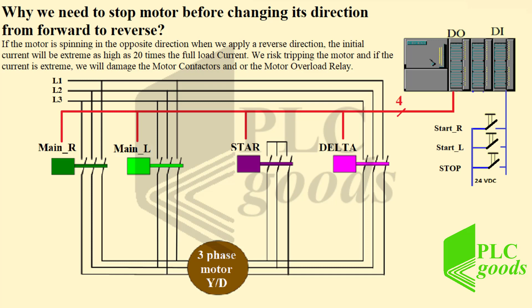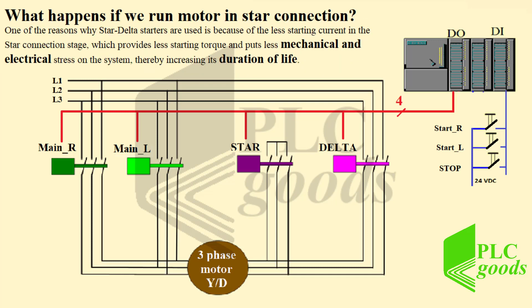What happens if we run motor in a star connection? One of the reasons why star delta starters are used is because of the less starting current in the star connection stage, which provides less starting torque and puts less mechanical and electrical stress on the system, thereby increasing its duration of life.